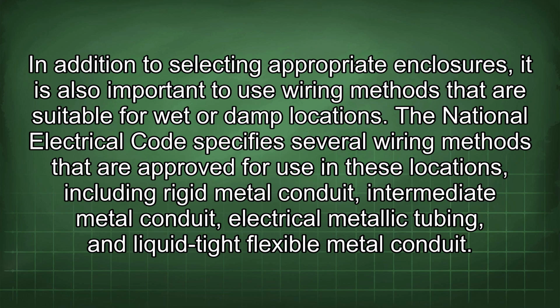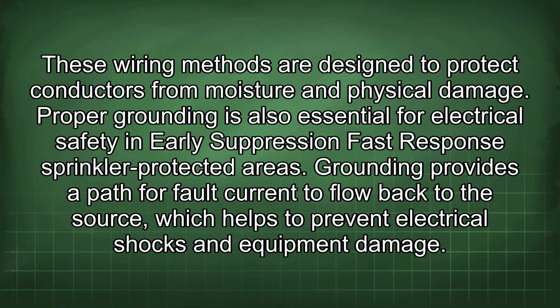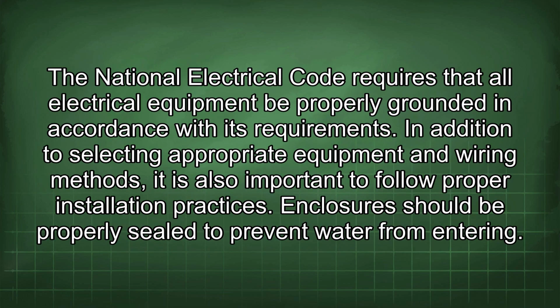The National Electrical Code specifies several wiring methods that are approved for use in these locations, including rigid metal conduit, intermediate metal conduit, electrical metallic tubing, and liquid-tight flexible metal conduit. These wiring methods are designed to protect conductors from moisture and physical damage. Proper grounding is also essential for electrical safety in early suppression fast response sprinkler protected areas. Grounding provides a path for fault current to flow back to the source, which helps to prevent electrical shocks and equipment damage. The National Electrical Code requires that all electrical equipment be properly grounded in accordance with its requirements.